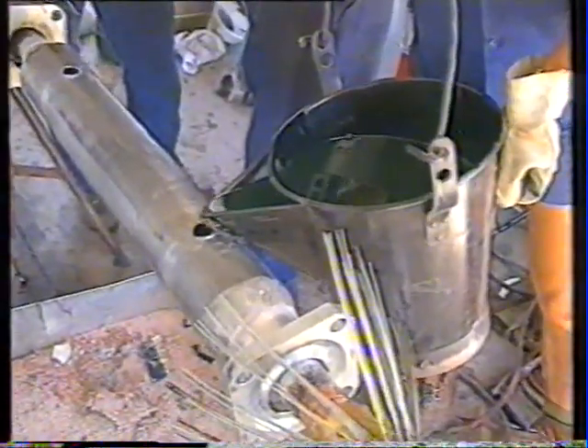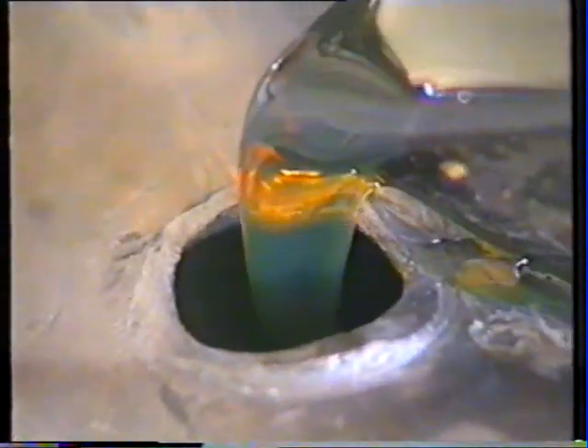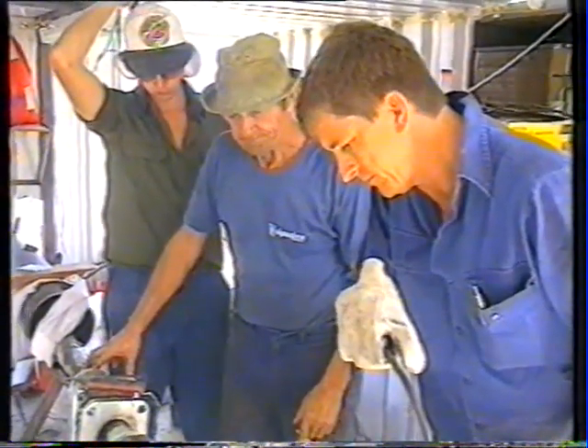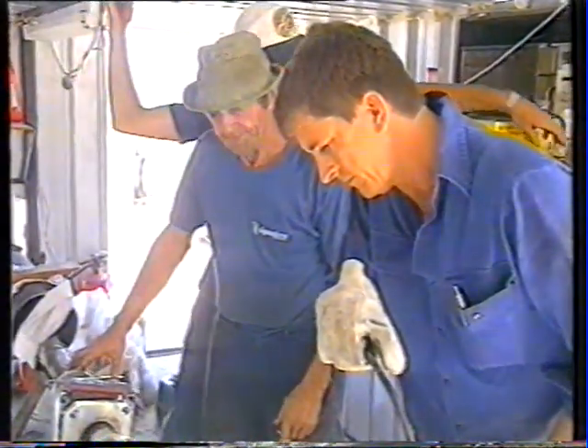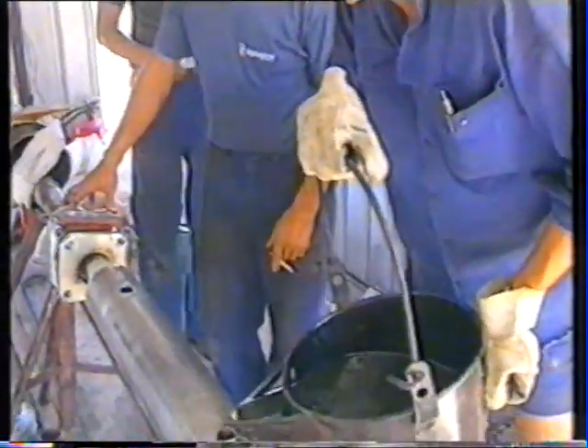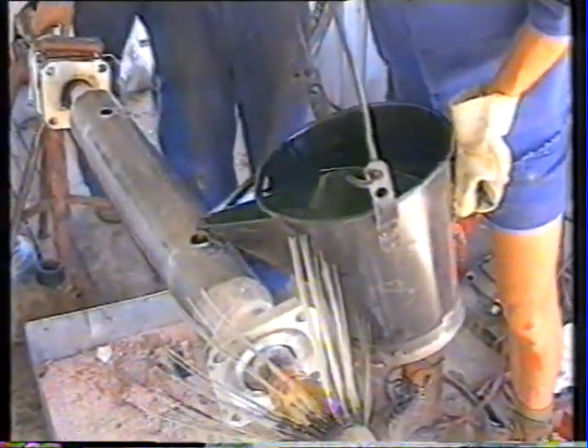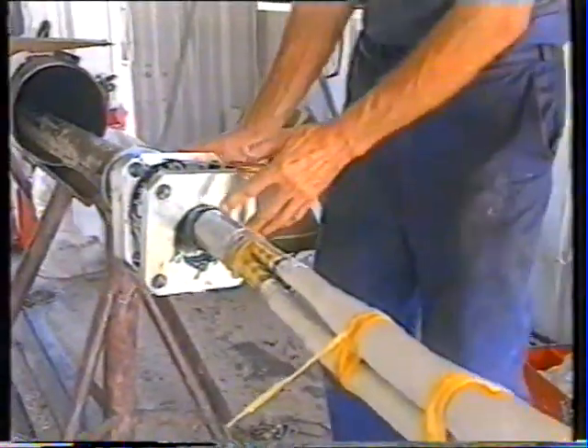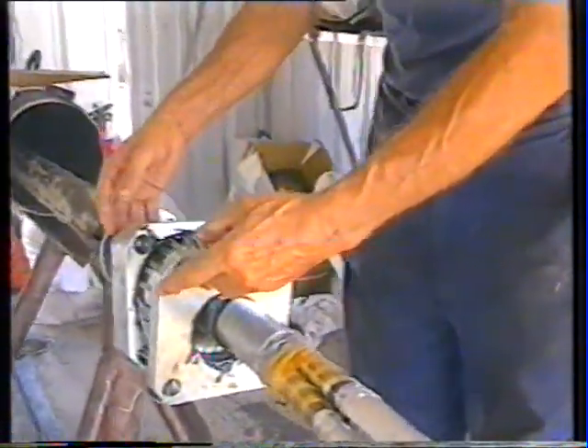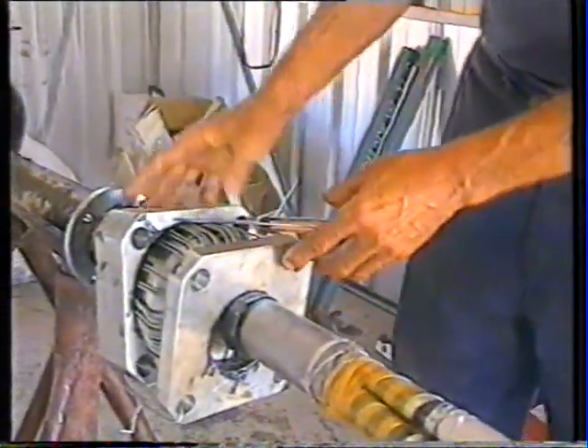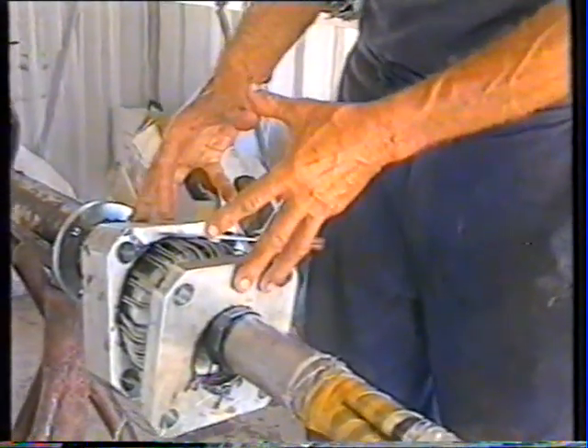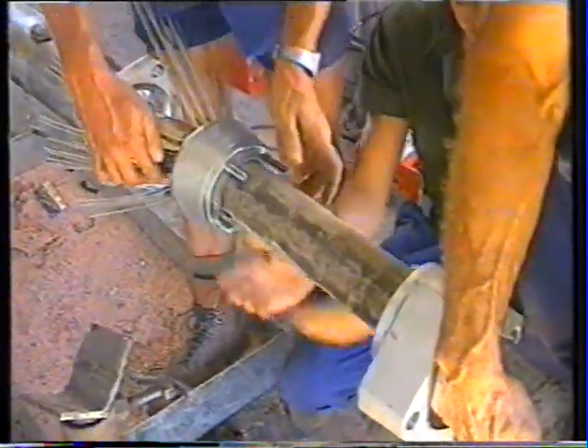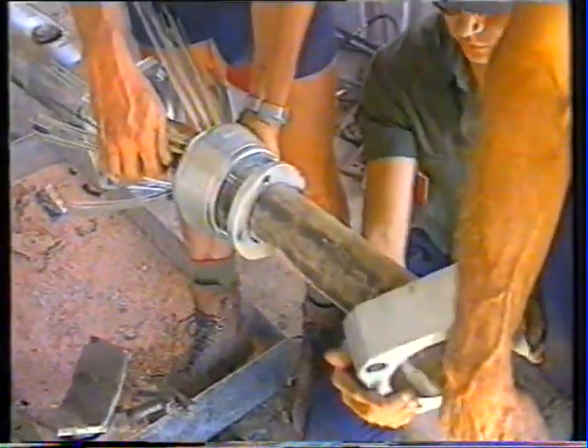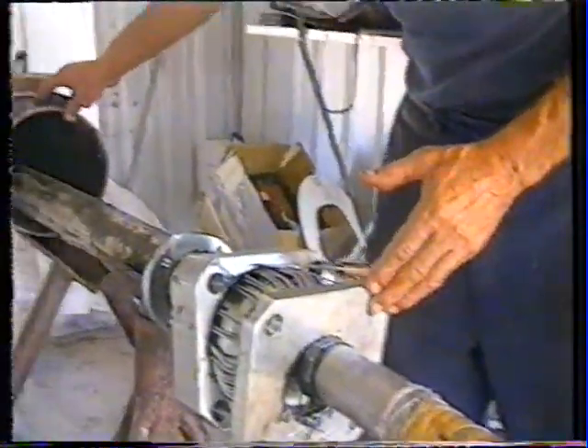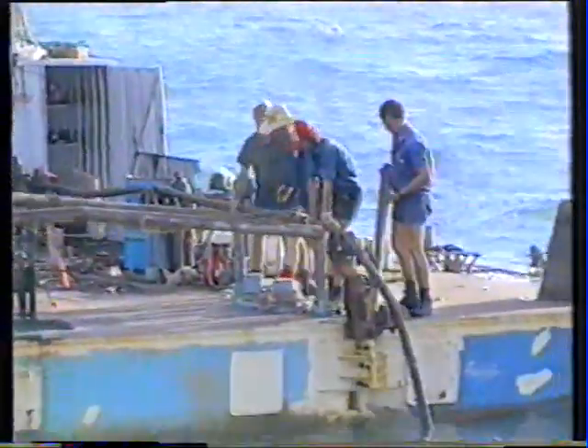And then we fill this sleeving up with oil, and it goes cold, and we top it up again, and then we seal the sleeving. The joint is complete. And then we put the protection box on. I don't know how you're going to explain this, but the box, we got 4 bolts come through here. When we tighten up, this pulls together, and that's the seal. And then we pull the box over the top and join the two ends, and then we fill this box up with compound.